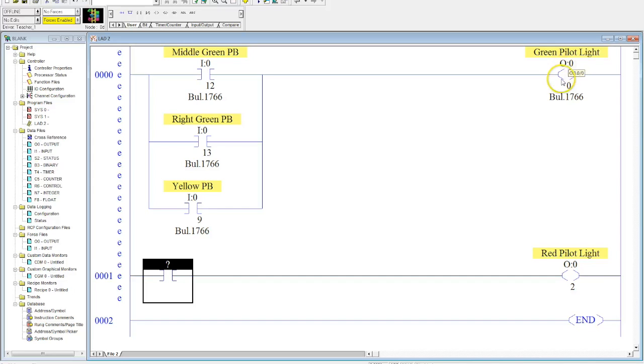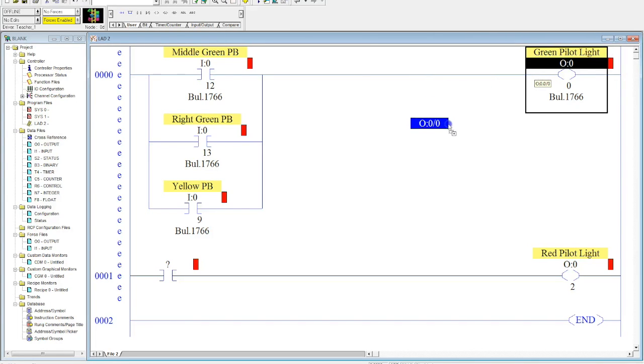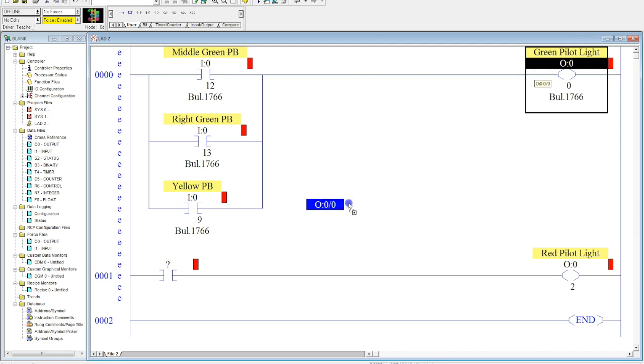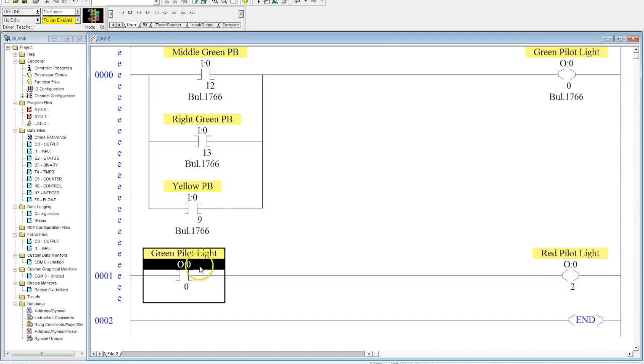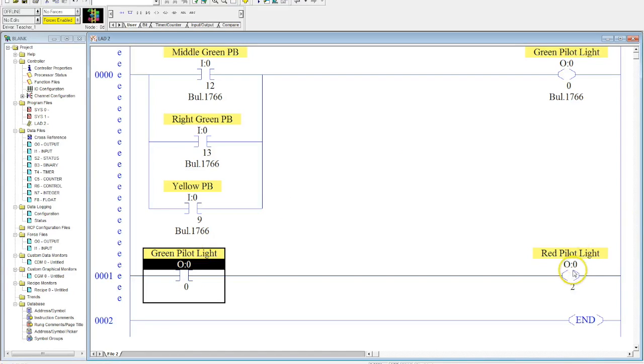Then, what I'm going to do is add a new input in here. Now, this input is going to be a contact off of the green pilot light. So, watch how I do this. I click on the address and drag the name down, and you can see that the address is actually coming with me. Wait till this turns green, drop it down. Now, this has the same light as this. So, this acts as a contact off of this output. So, whenever this is true, this will turn true, and then, of course, turn my red pilot light on.